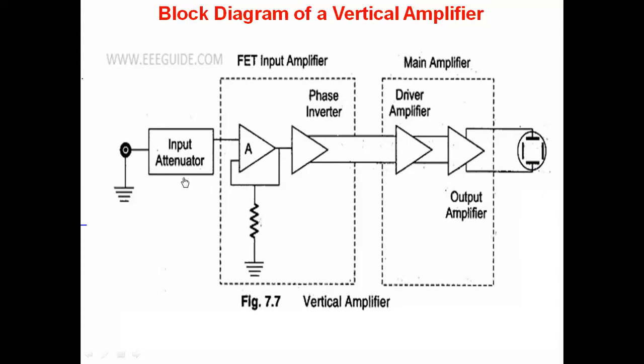After the input signal is attenuated, it is given to the FET input amplifier. In the FET input amplifier we have a FET source follower. It separates the input side and the output side because it offers high input impedance. That's why it isolates - if any loading effects occur, those will be reduced. That's why we use the FET source follower.